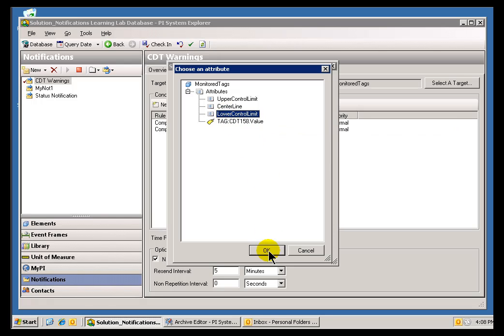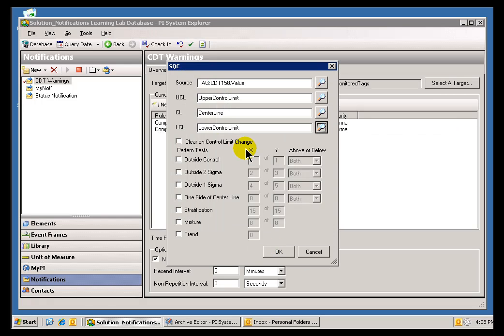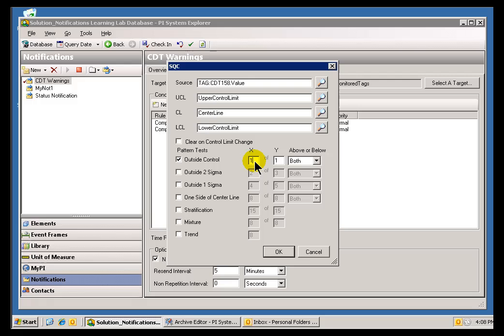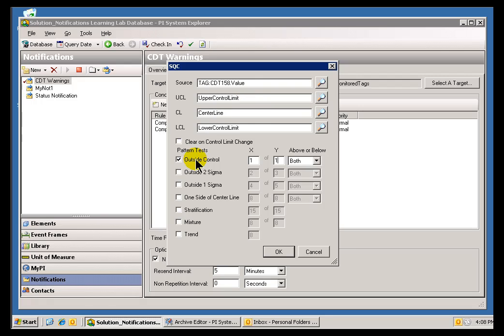There's our Lower Control Limit. Now, for the Pattern you want to use, you can choose any of these that you like. These are the standard Western Electric Test Patterns. The outside control is the standard three standard deviations test. This essentially means if one out of one value coming in from this Element Attribute is outside three standard deviations, then we send the Notification.